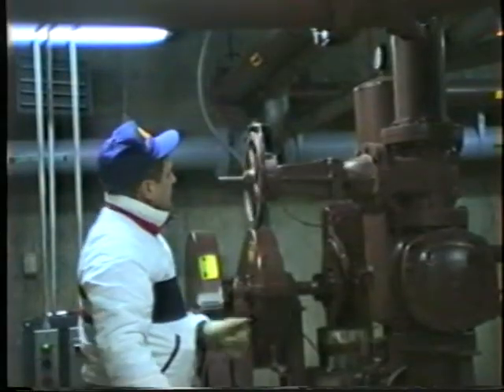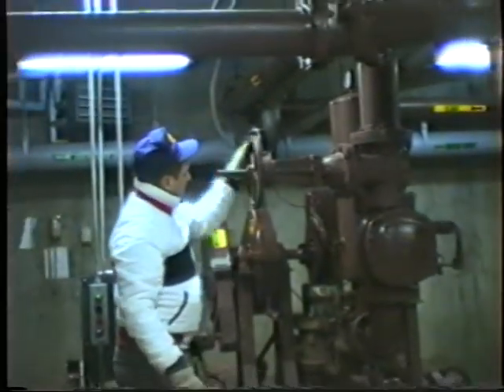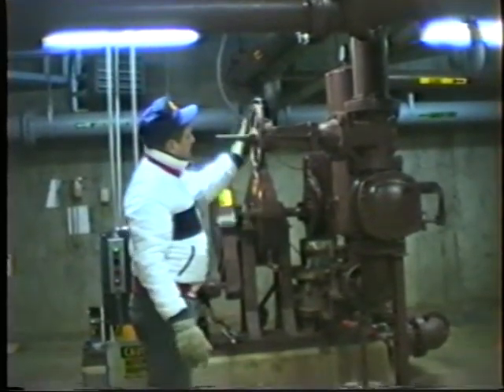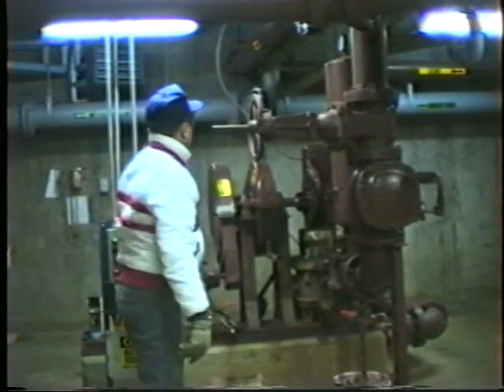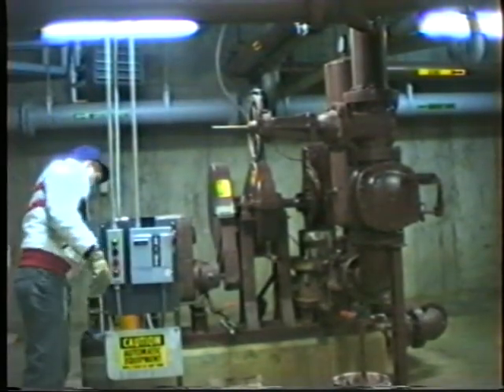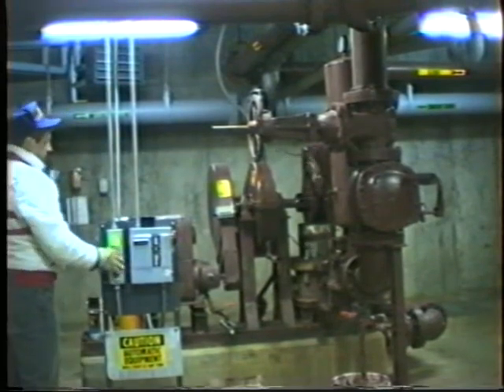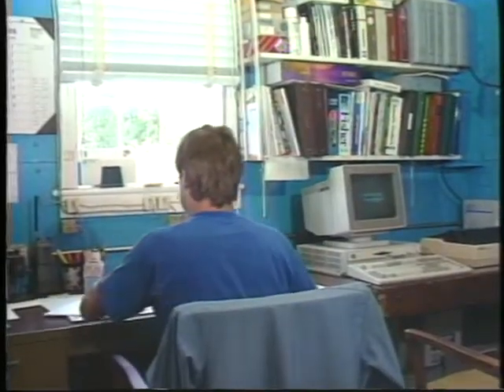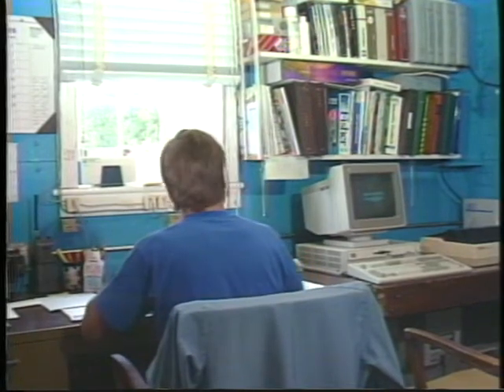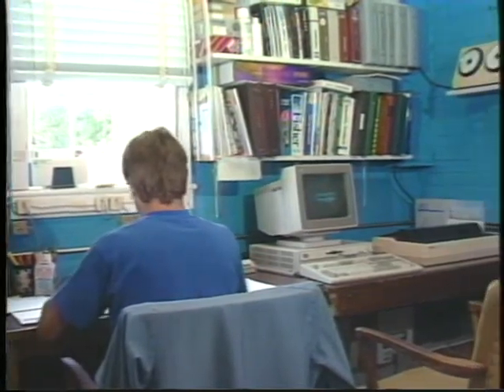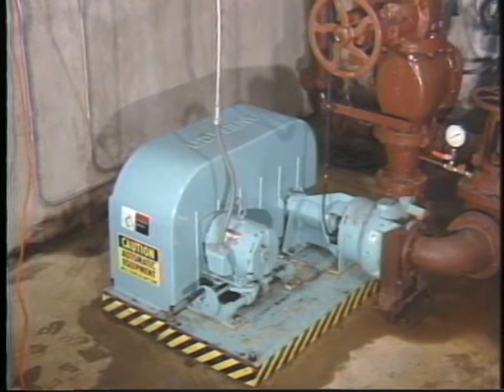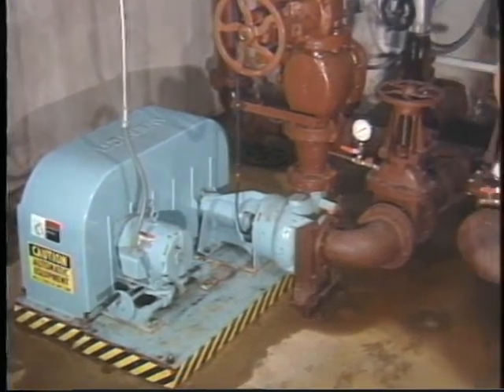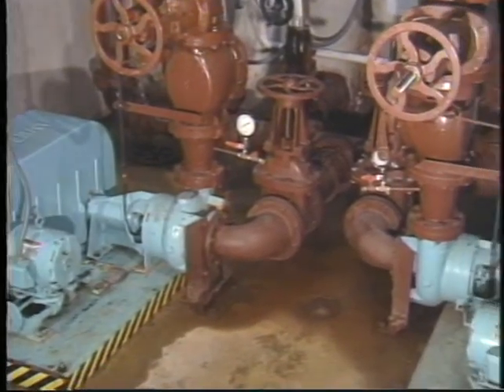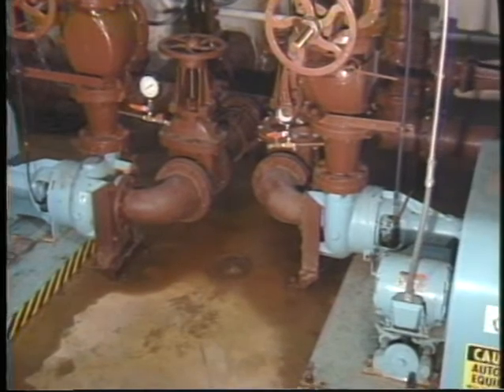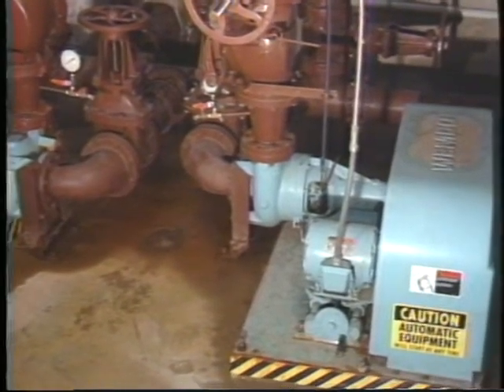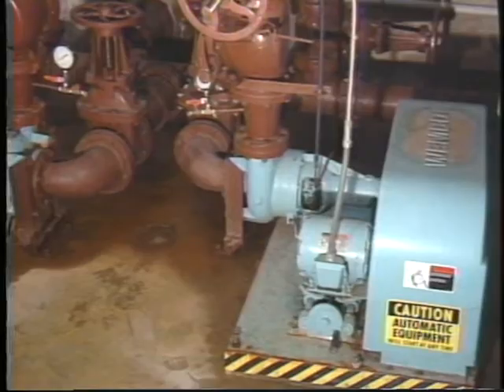It is important to note that you must have all the necessary valves open before starting a positive displacement pump. Failure to do so will result in serious damage to the pump or to the piping system. As with all equipment, you need to become familiar with the unit by reading and understanding the operating instructions before you attempt to operate that equipment. Centrifugal pumps that are designed for solids handling may also be used for moving or removing solids. The centrifugal pumps are used commonly for removal of secondary sludges and for circulating the contents of primary anaerobic digesters.